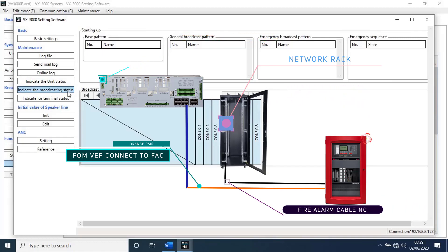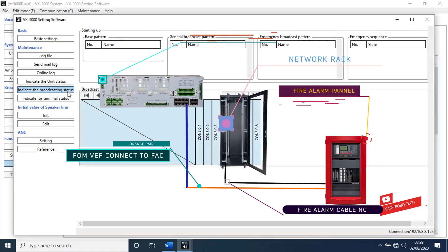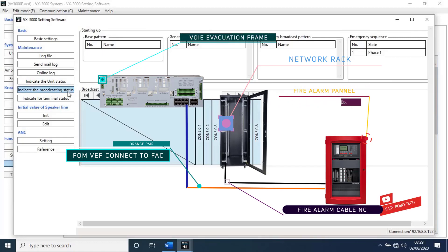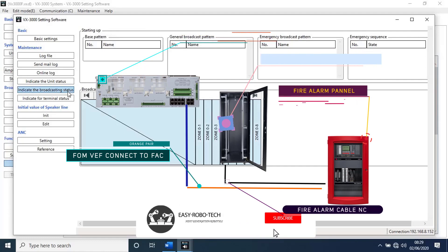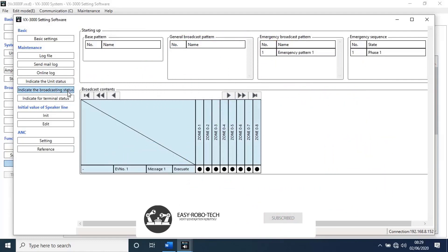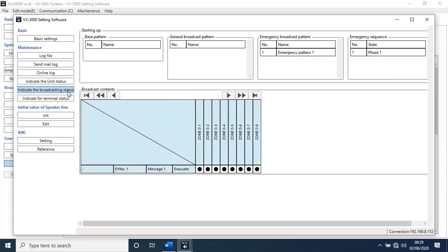I never recommend type 2 interfacing with fire alarm system because it's not the professional way. Let's try to give emergency signal. As you can see, below all zones a dot appears. It means the zones are receiving signals.